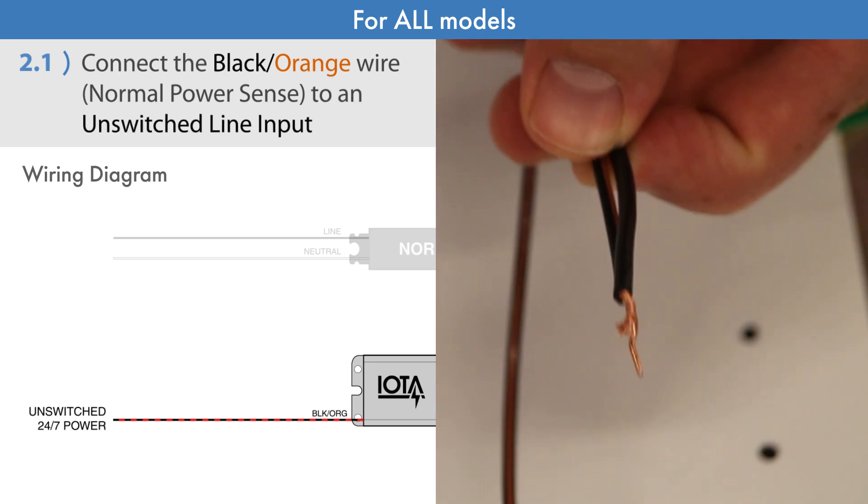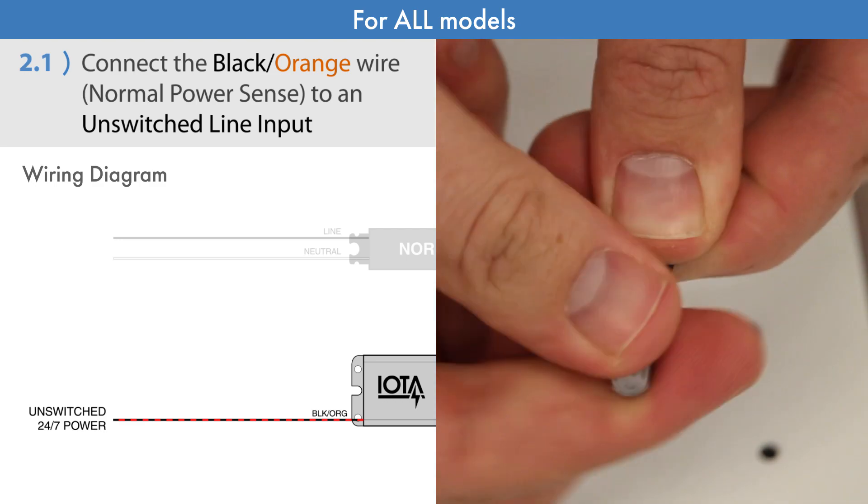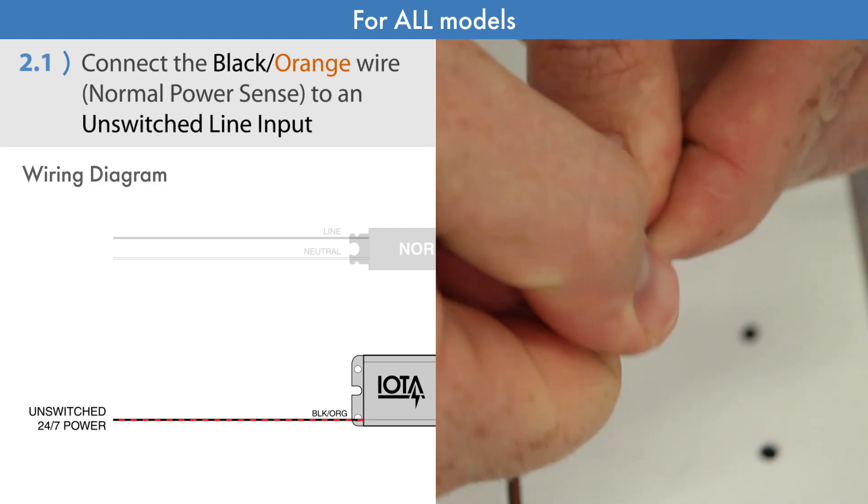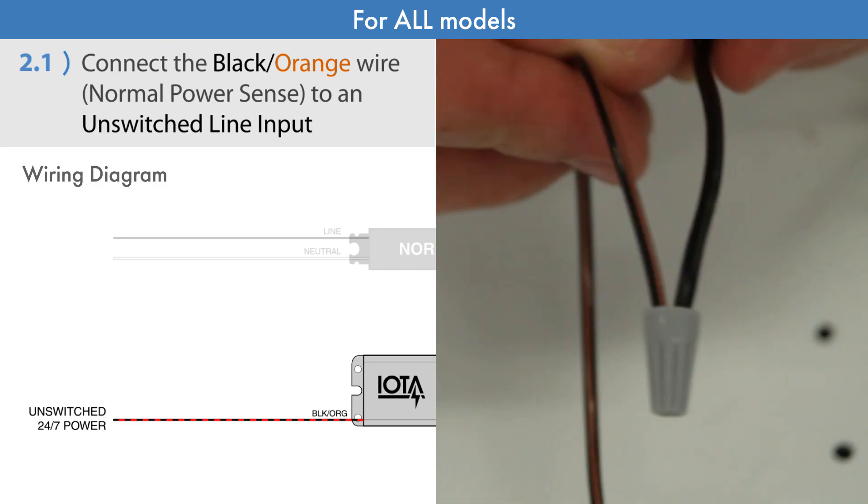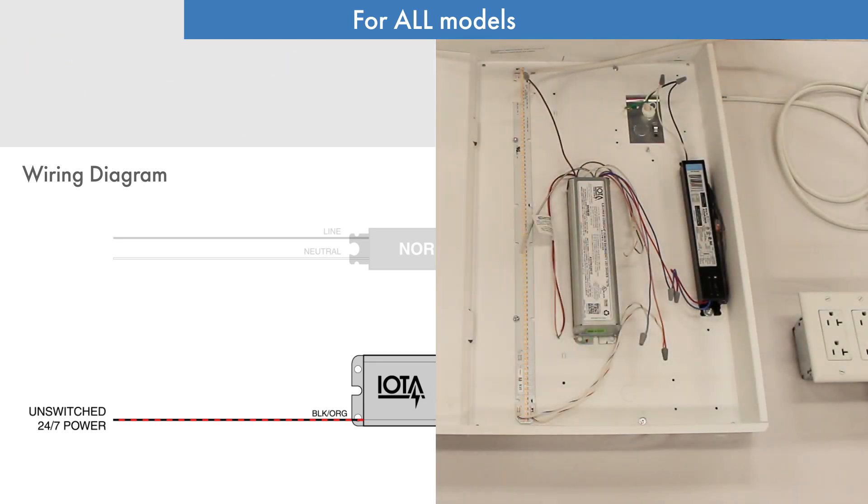If you are using a wall switch on your LED fixture, make sure that the black-orange wire is connected ahead of the switch. The next steps are for ILB-CP standard models only.